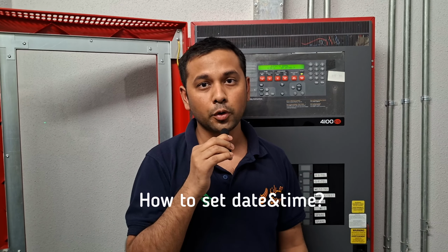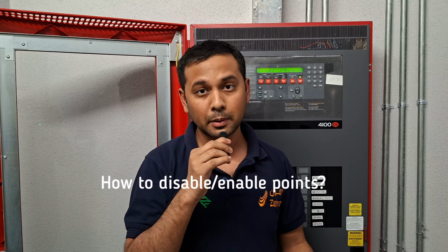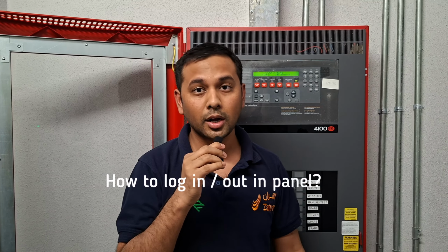So in this video you will understand how you can operate the Simplex 4100ES panel. Later in this video I will tell you how you can set date and time, how you can disable the points and enable them also, and how you can log in to the panel. These are three things that are very necessary for every technician or anyone who is working at the site.